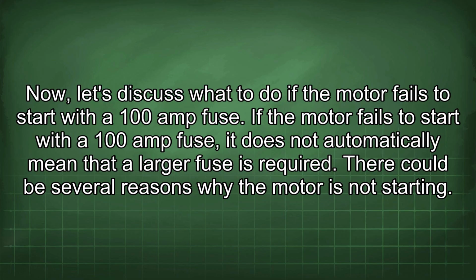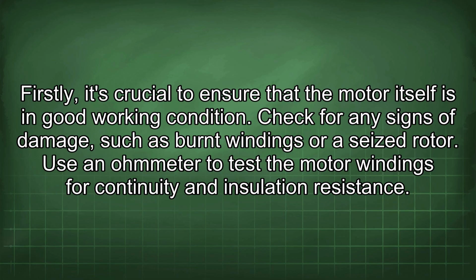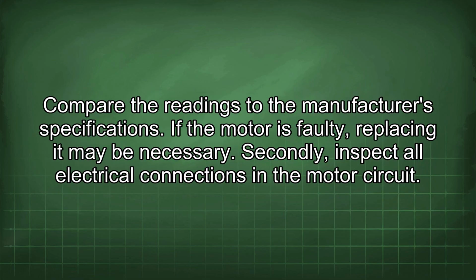Now, let's discuss what to do if the motor fails to start with a 100 amp fuse. If the motor fails to start with a 100 amp fuse, it does not automatically mean that a larger fuse is required. There could be several reasons why the motor is not starting. Firstly, it's crucial to ensure that the motor itself is in good working condition. Check for any signs of damage, such as burnt windings or a seized rotor. Use an ohmmeter to test the motor windings for continuity and insulation resistance. Compare the readings to the manufacturer's specifications. If the motor is faulty, replacing it may be necessary.